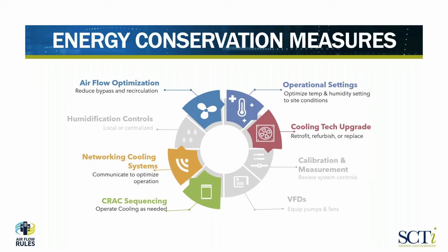And then we look at operational settings. So what's the temperature, what are the humidity set points that you have on your CRAC units? How much can we push those up? Because the higher we can push those from a temperature point of view, the more efficient your cooling unit is going to run, and equally so, the less energy it's going to consume.